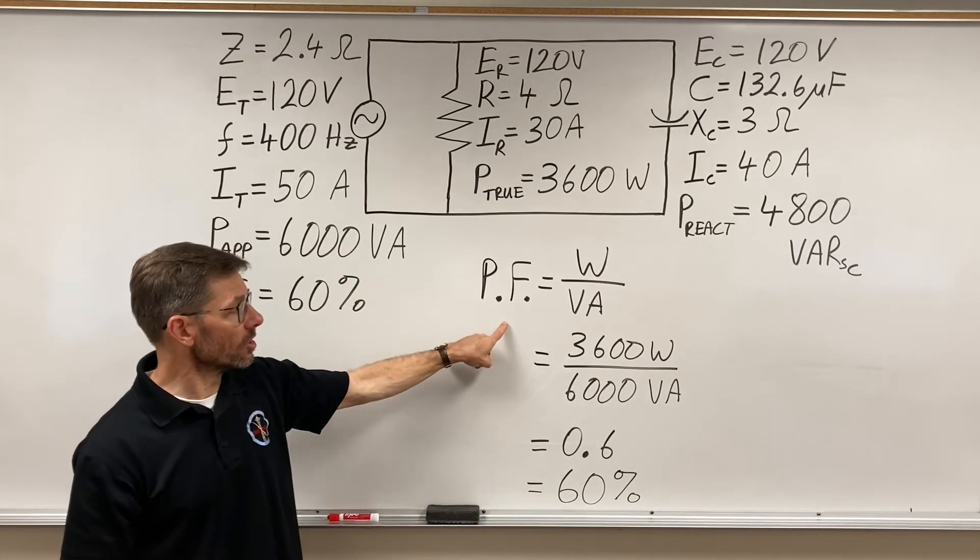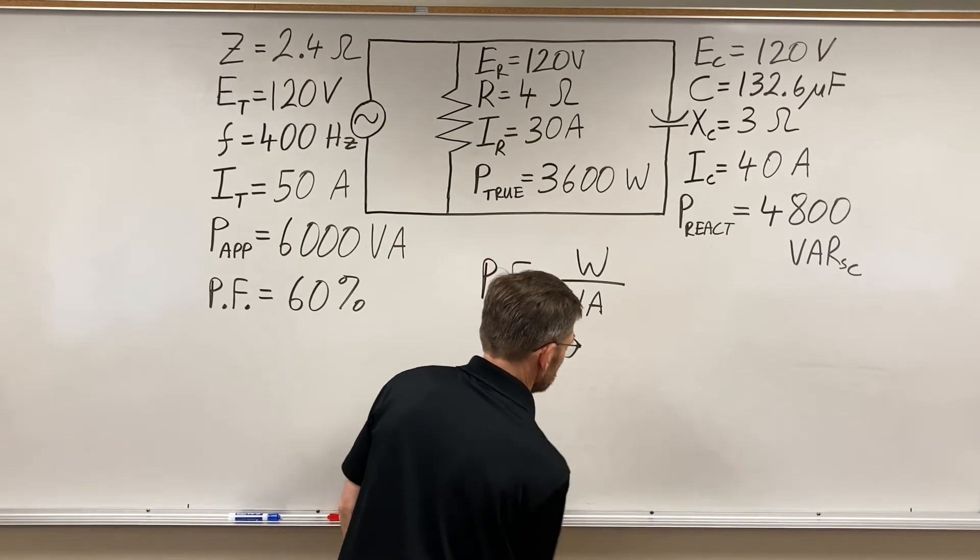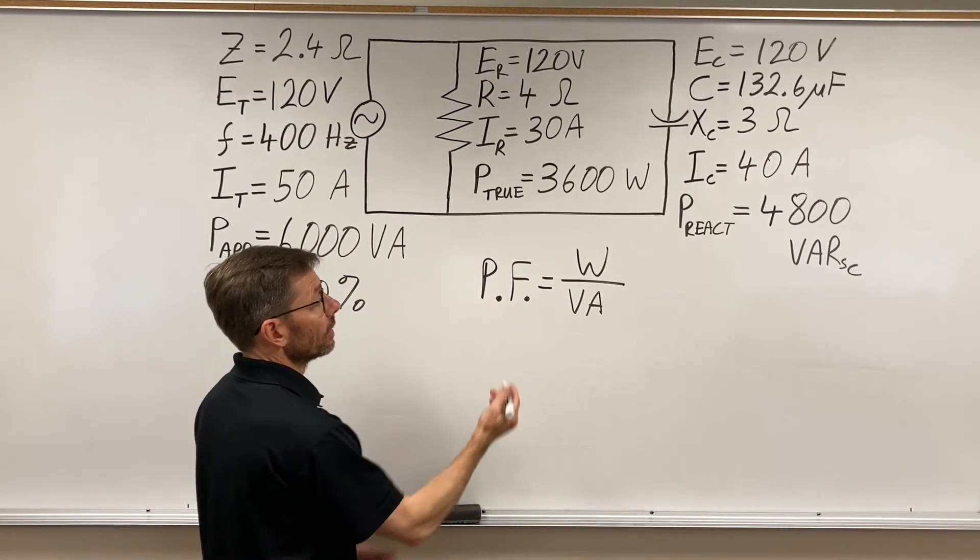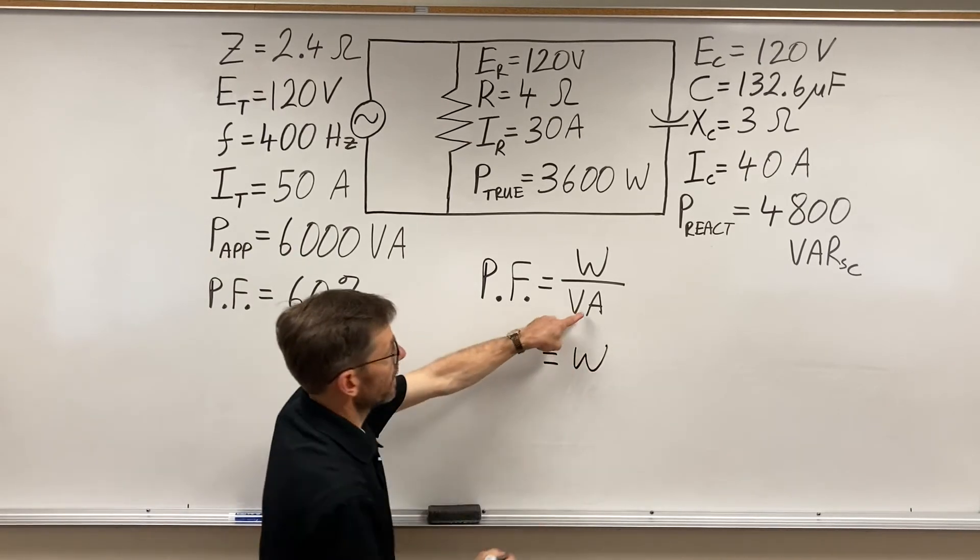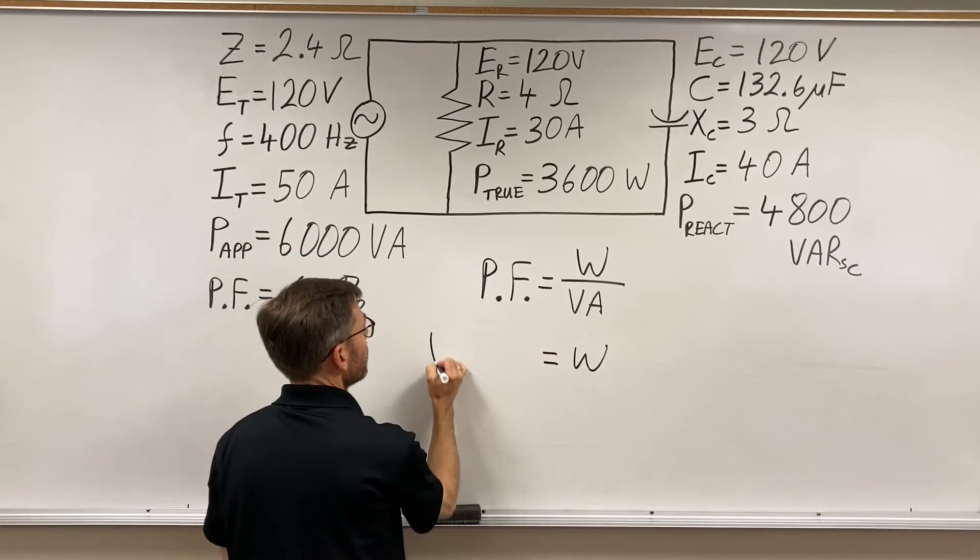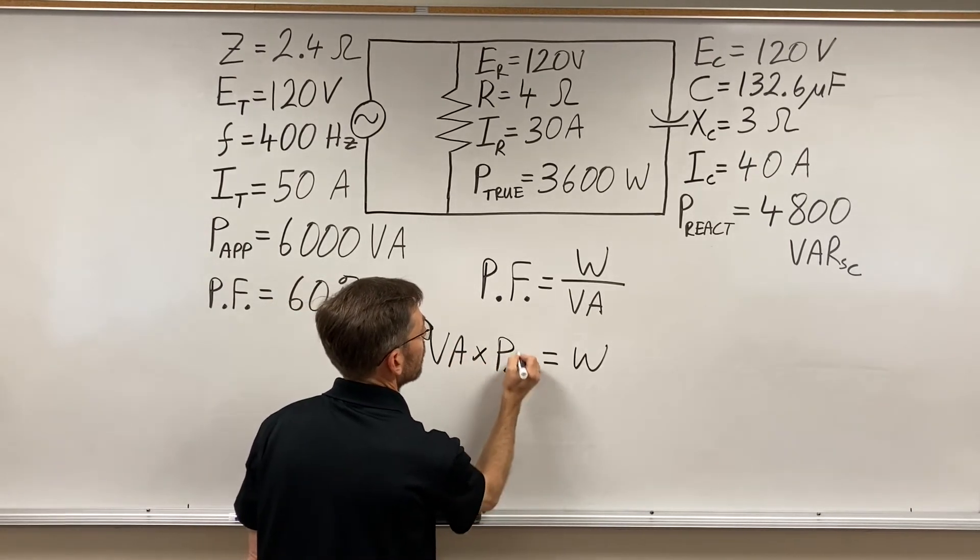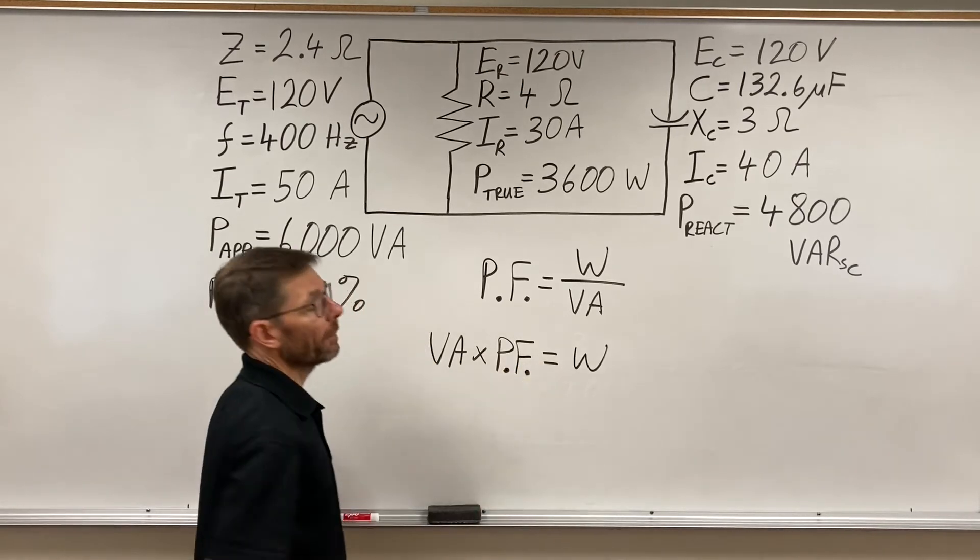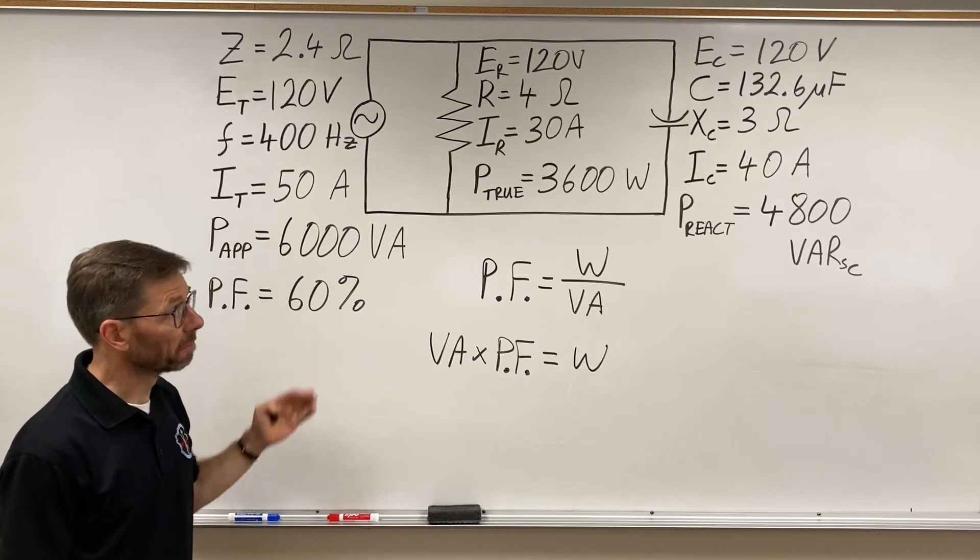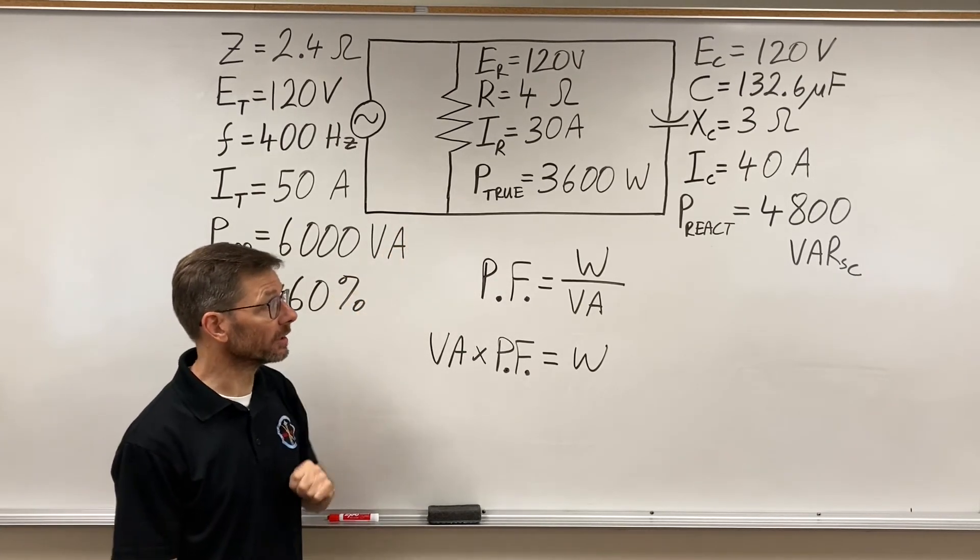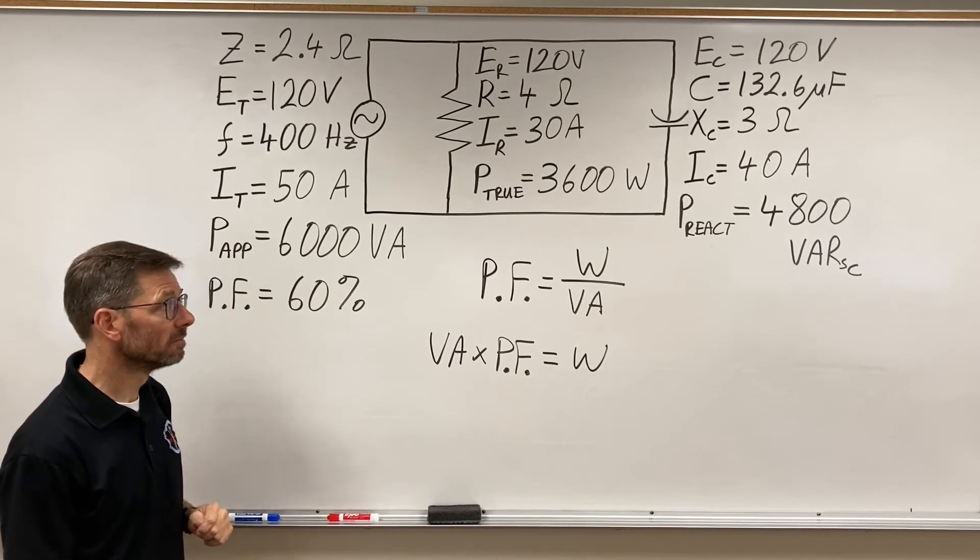We can take this equation and rejigger it, if you will, algebraically rearrange it. Would my watts, take the VA to this side, not be my VA times my power factor? So if I know my volt amps and my power factor, can I figure what my watts are? No problem. Just take your VA times your power factor.